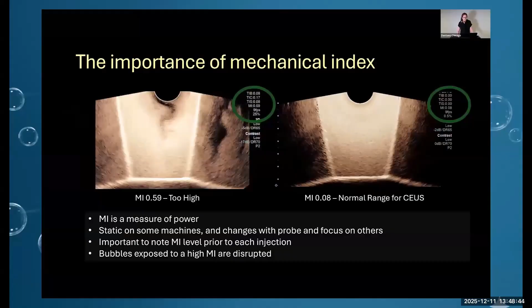So mechanical index is a measure of power. It's static on some machines and changes with probe and focus on the others. It's important to note the mechanical index level prior to each injection. Bubbles exposed to a high mechanical index are often disrupted.